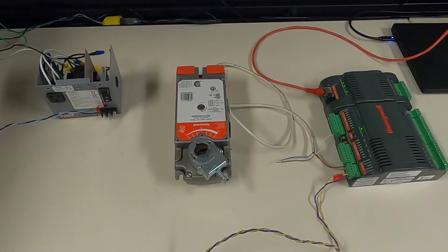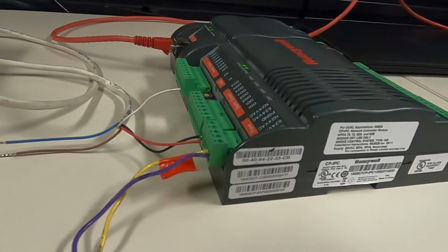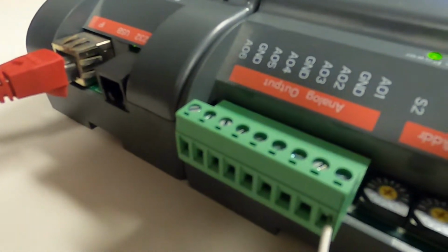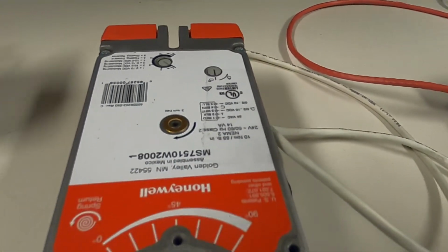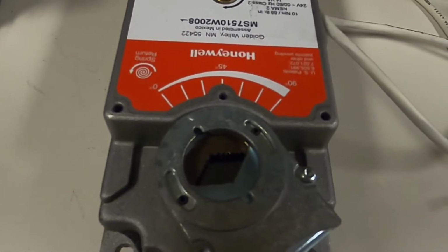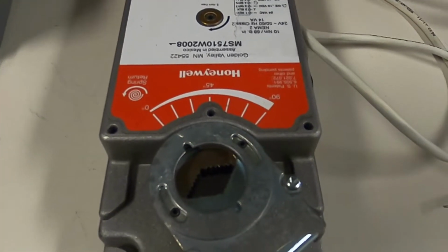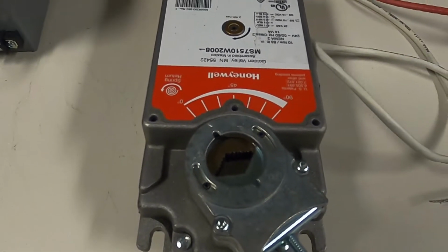Let's see a simple illustration of how it is actually wired and how it reacts to your control signal on field. So to demonstrate analog output, I have a quick setup of a transformer, an actuator, and a controller to which an analog output is connected with 24 volts being supplied to the actuator. So as it denotes, this is right now in 0th position, and I'm going to trigger a 5 volt signal to this to see if the actuator moves to half its way.